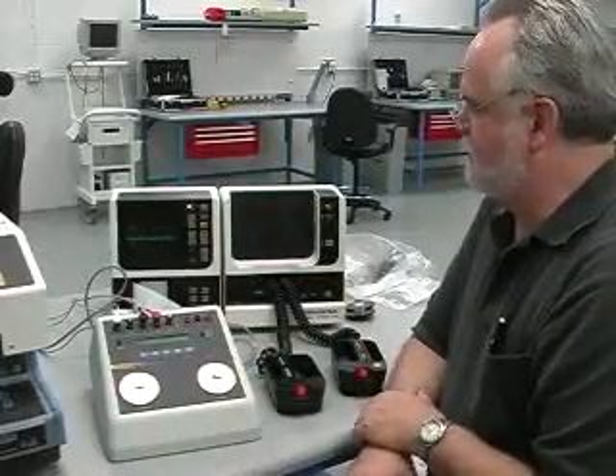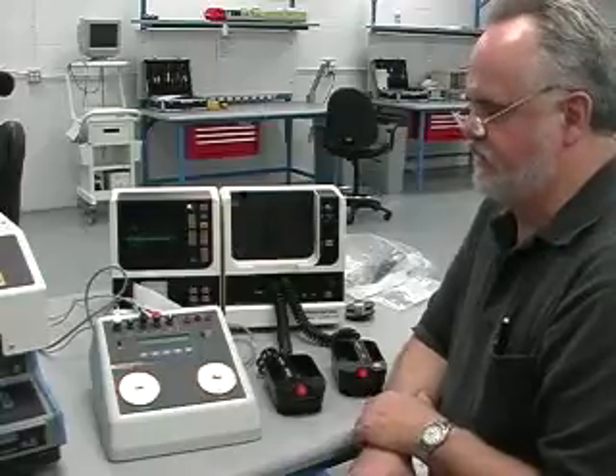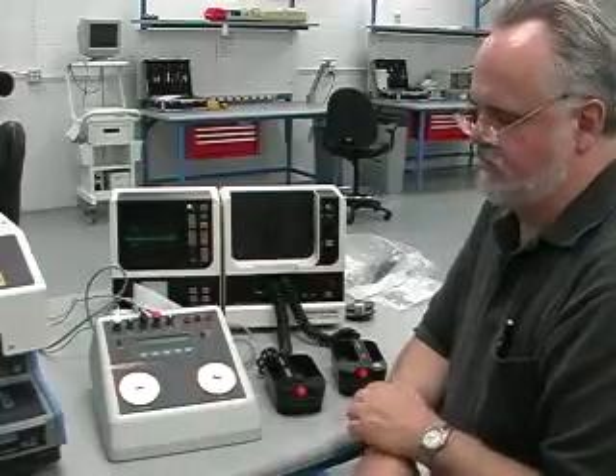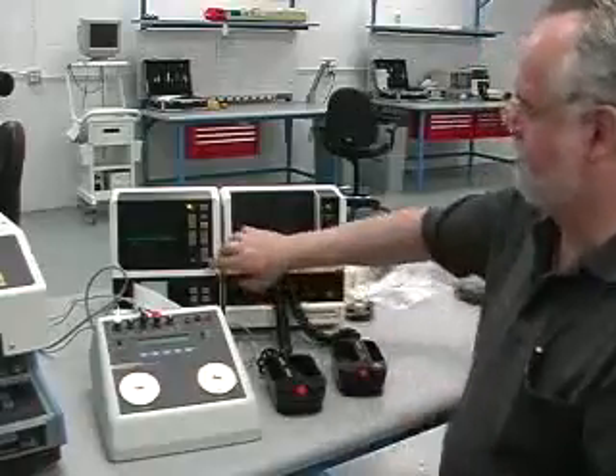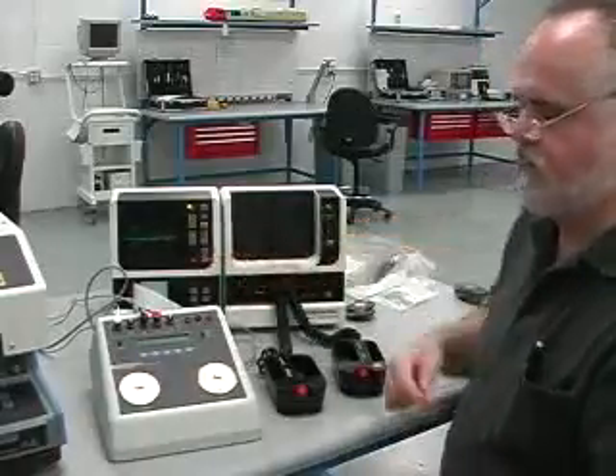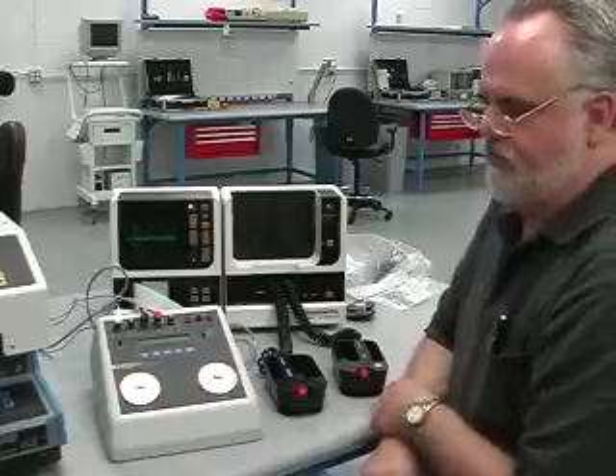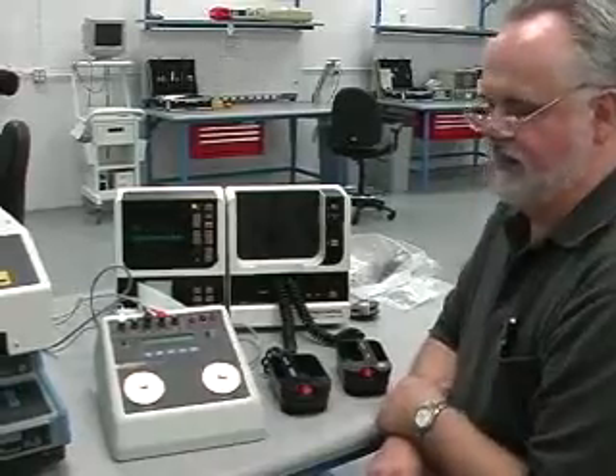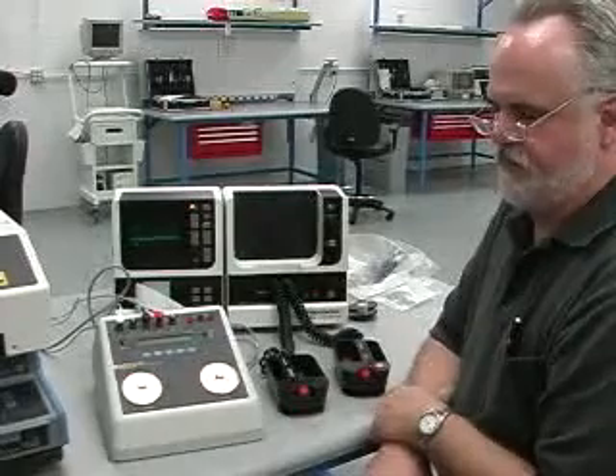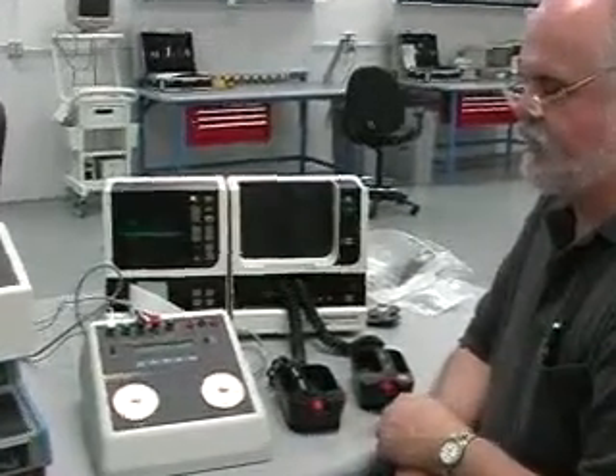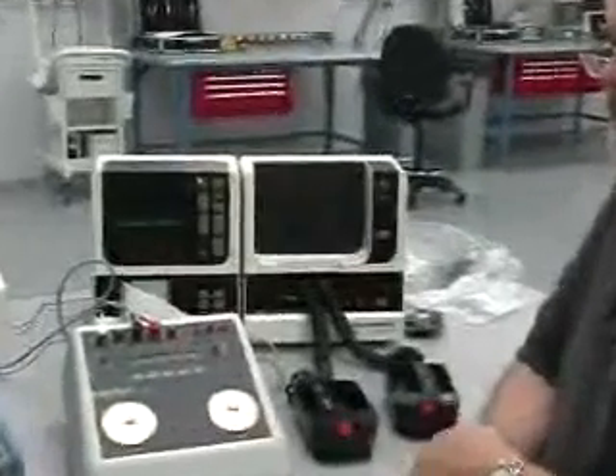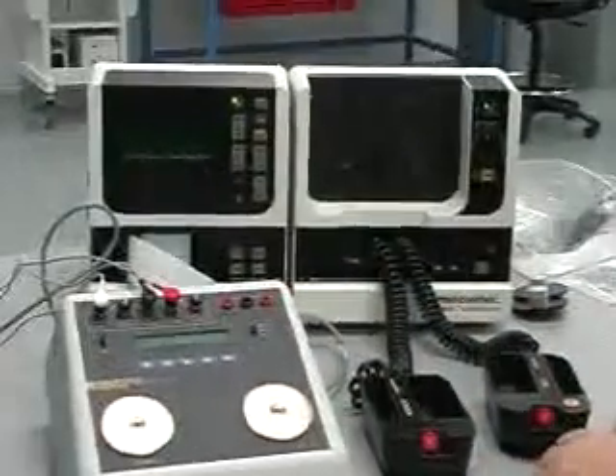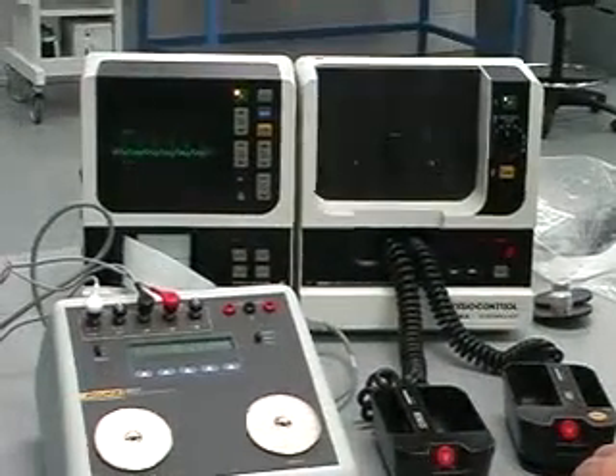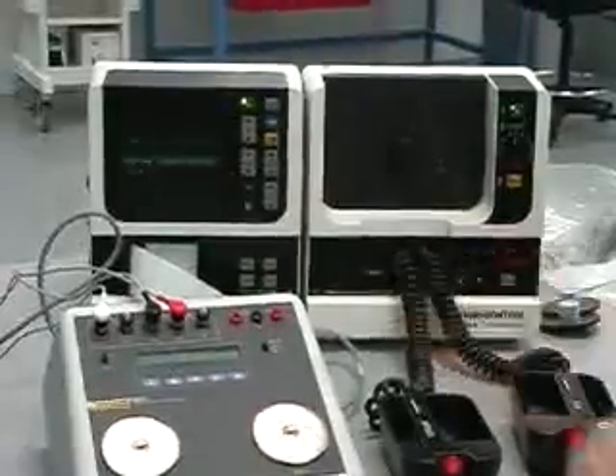I know that some defibrillators, especially the solid state transfer relay units like the MRL, some of their Model 50s, the PIC 50s and PIC 30s, sometimes they will be able to discharge prior to the R wave, and in that case, you're going to see a reading that's obviously a much smaller value on the analyzer.